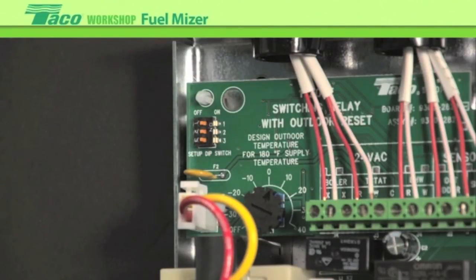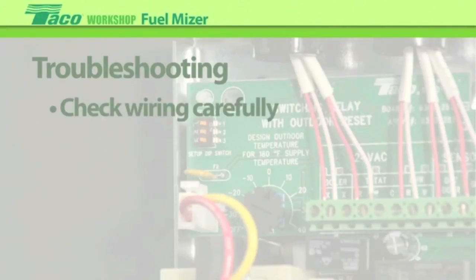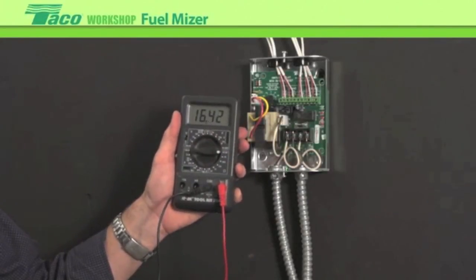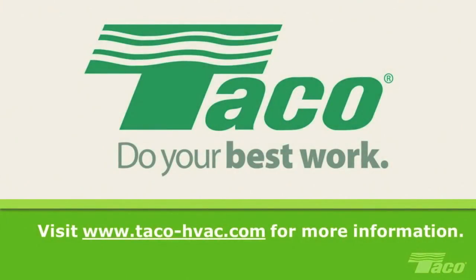We're all set to go — turn it on and check the system out. From experience, the number one problem in the field is low voltage wiring. If there is a problem with the control, before jumping to conclusions and condemning it, it tends to be a field-related wiring issue. Another good thing would be to check your sensors using a good quality digital ohm meter — undo the sensors, measure the resistance, and look in the chart to make sure everything is where it's supposed to be. Visit us online for more support and information on the full line of Taco systems and components.